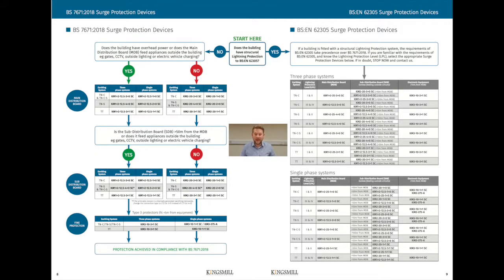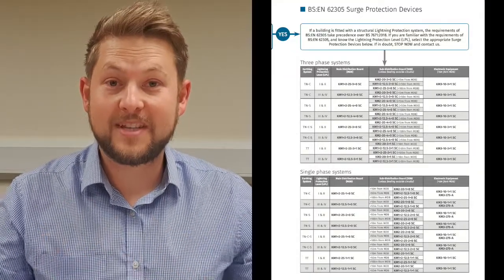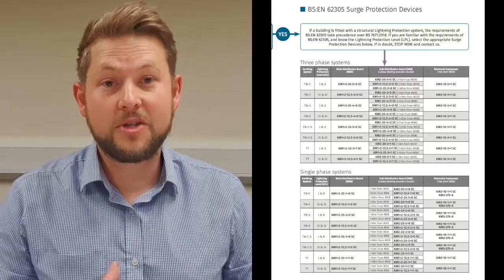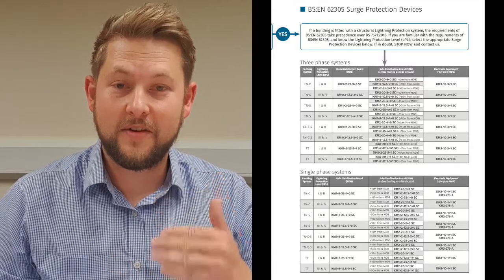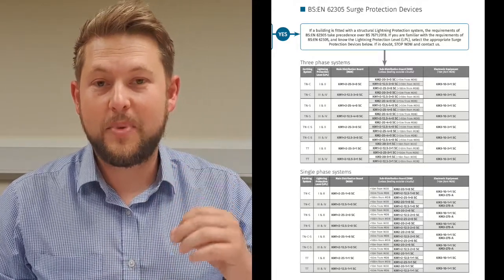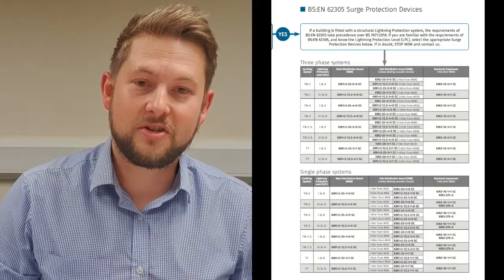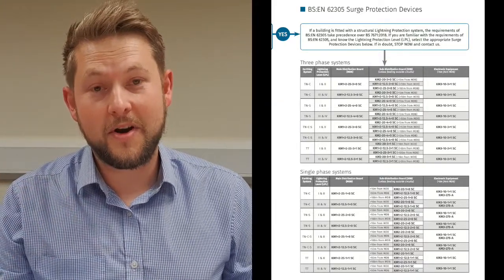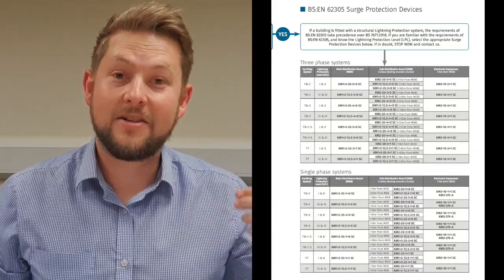The first question we're going to ask is: does the building have structural lightning protection installed to BS EN 62305? If the answer is yes, then we move towards a 62305 type device. Within the guide we have a table which gives all the different types of device dependent on the level of lightning protection installed and also the earthing arrangement and phase.